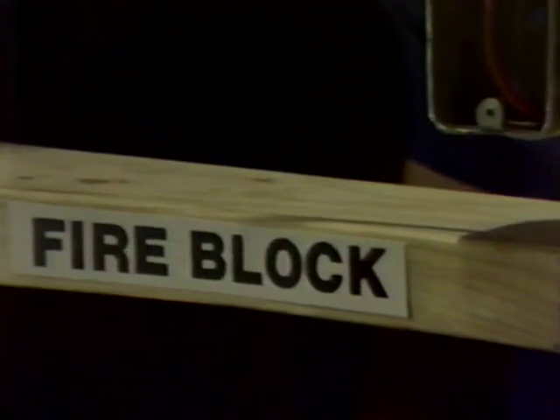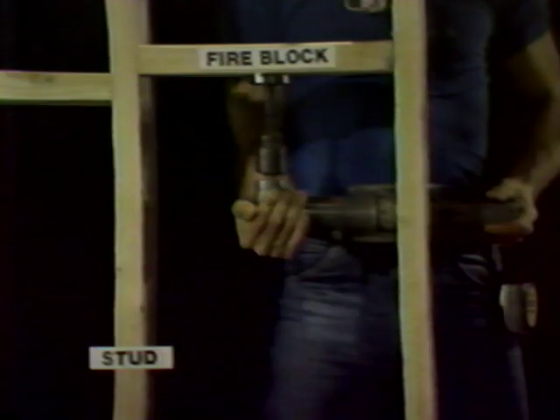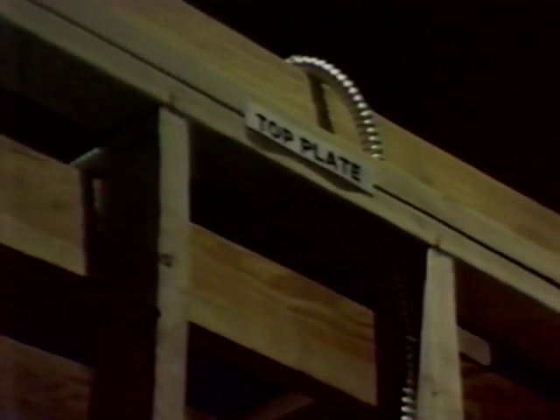Whenever drilling a fire block, always try to drill about 6 inches from the end to avoid hitting nails or splitting the fire block. The fire block should always be drilled instead of removing it. Next, drill the top plate, but before you drill, carefully inspect for any nails, wiring, plumbing, or any other object that might be in the way. The preferred size hole to drill is 2 9/16 inch. A right-angle drill will have sufficient power to drill a hole that size. Both the drill and drill bit can be rented from your local tool rental firm. When drilling overhead, it is always advisable to wear safety goggles.